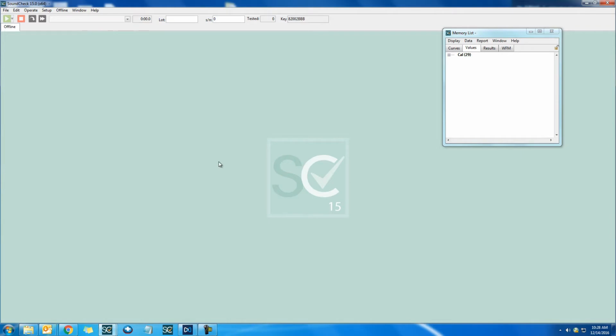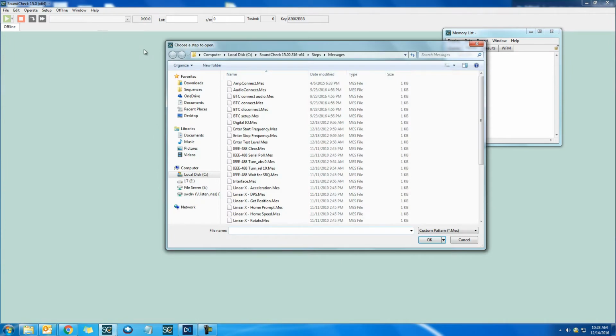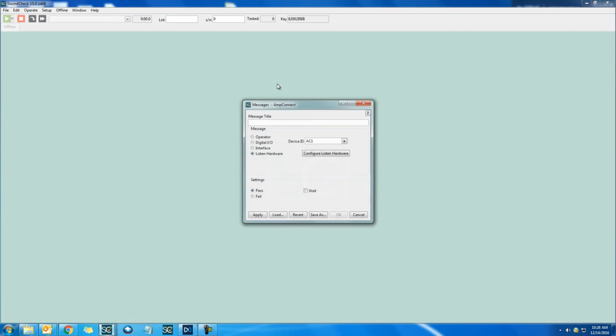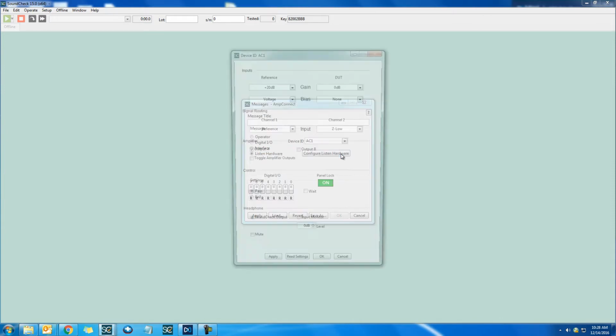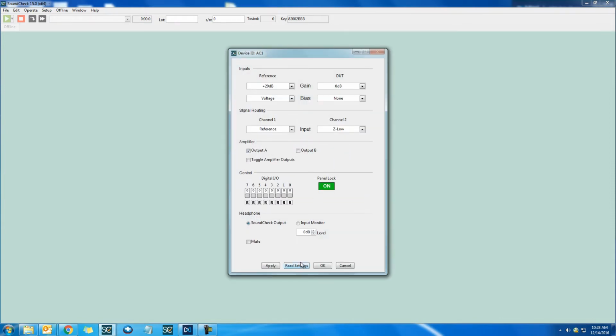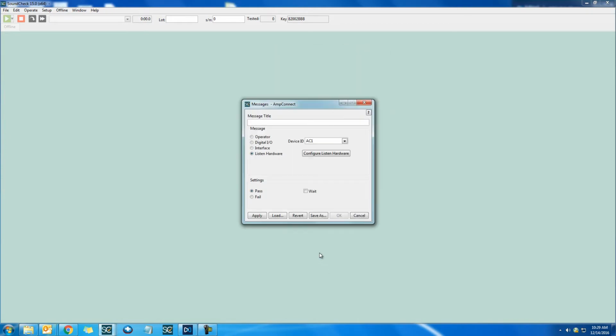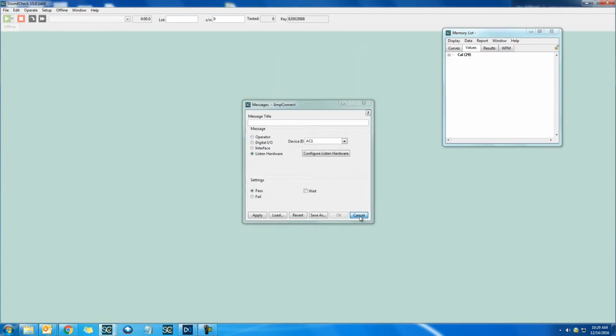Alternatively, we can run an offline message step to set up the Amp Connect. We'll choose Amp Connect, select our device ID, and click Configure Listen Hardware. On this page, we can just click on the Read Settings button. So everything here looks good because everything was already configured on the front panel of the Amp Connect. We can just hit OK and then cancel the message step. We're now ready to run calibration.